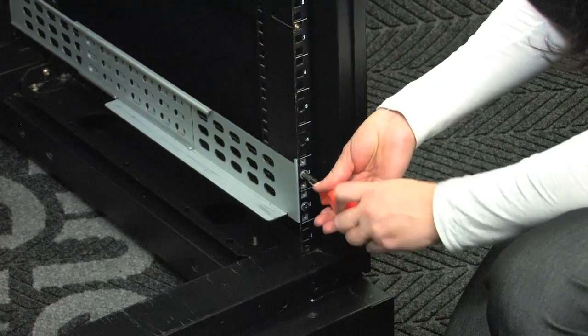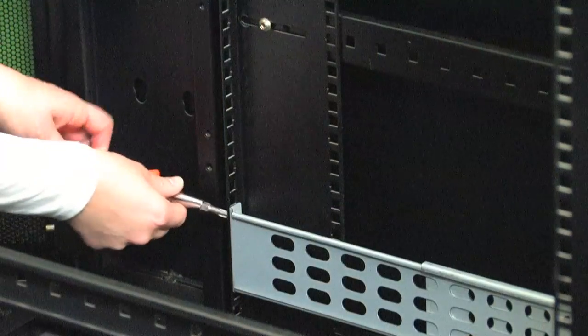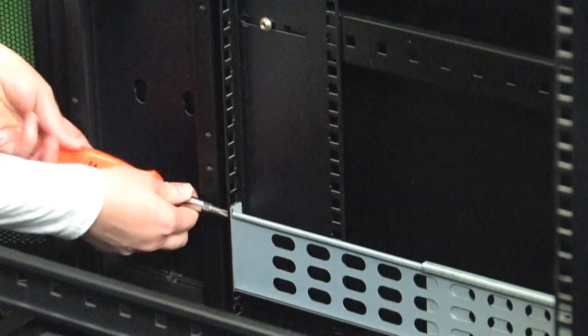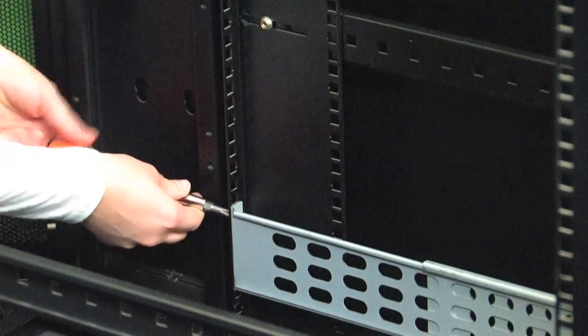Use the flat-headed screws to affix the rails to the desired U position, preferably at the bottom of the rack. Reserve the top and bottom holes for affixing the mounting ears. Go to the rear of the rack and affix and repeat the process.